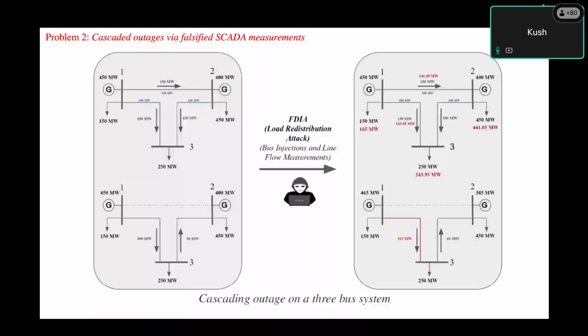So it sees that the redispatch is very different. 450 now it is just 65, right? But that 15 megawatt is good enough to cause an overload on transmission line three. So if for some reason transmission line one and two is lost, then the line between bus one and three will be overloaded by 15 megawatt, and that 15 megawatt is the overload relay tripping for this particular transmission line as well. You lose the entire 465 megawatt generator.